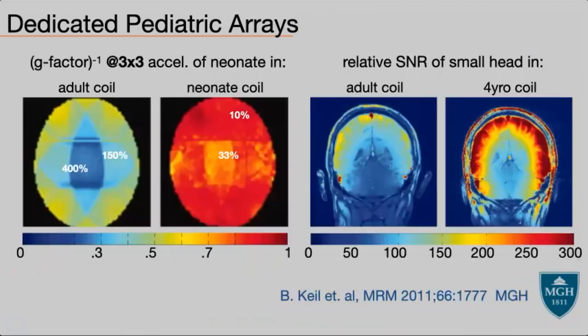Now this image is very important, this figure is very important. Take a look at the right-hand side. If you put a patient with a small head in a 4-year-old coil, the SNR would be significantly better than scanning the same patient in an adult coil. That's because the elements are just closer. But on the left side, you see the most remarkable result, and this is something we haven't talked about yet, called G-factor acceleration.